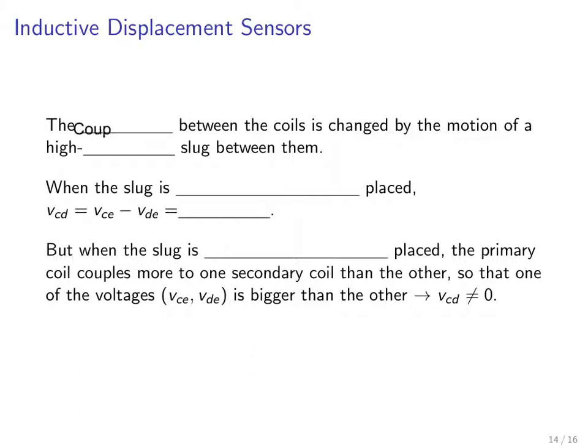The coupling between the coils is changed by the motion of this high mu slug between them. When the slug is symmetrically placed, then the voltage difference between the two outputs, VCE minus VDE, equals 0. But when the slug is asymmetrically placed, then the primary coil is going to couple more to one secondary coil than the other, so one of the voltages is bigger and we get a non-zero voltage output.